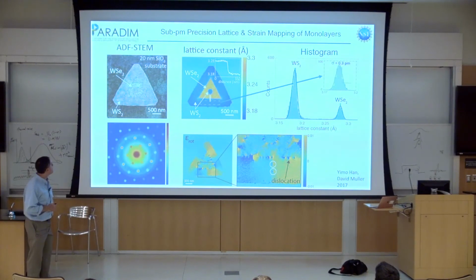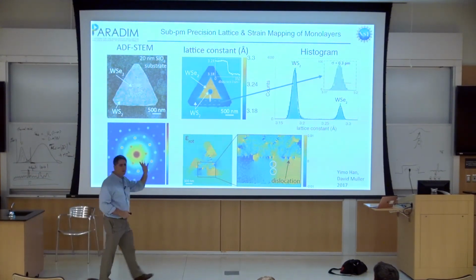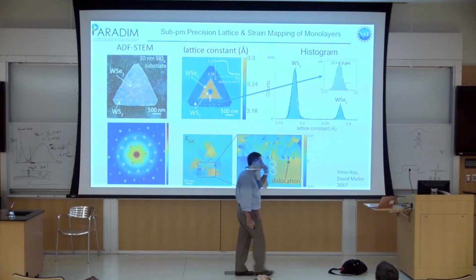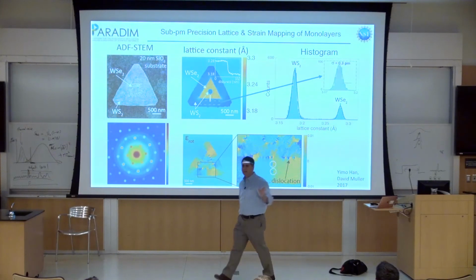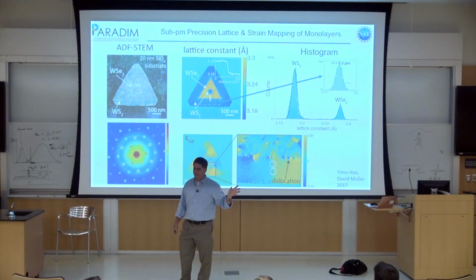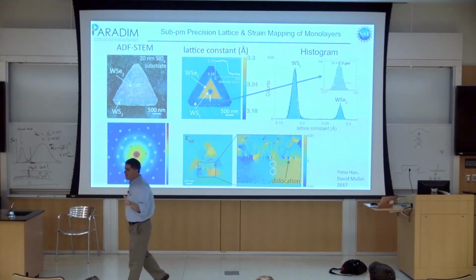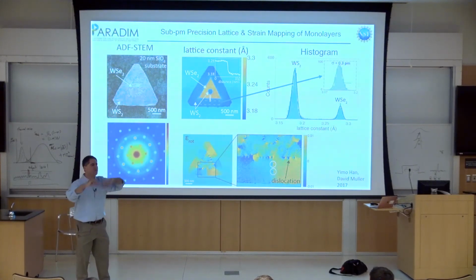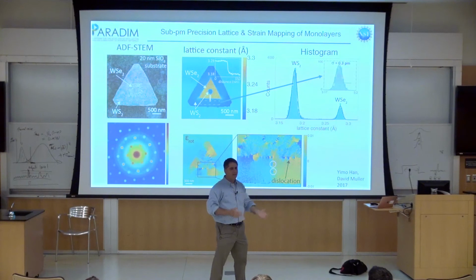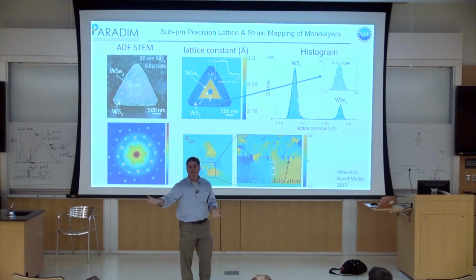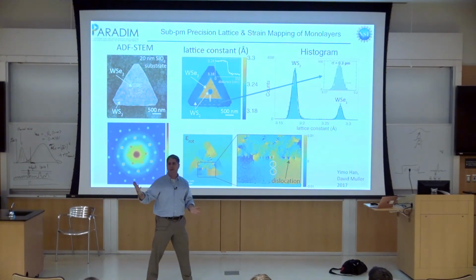I think in the interest of time, I should stop there. The two things I want you to remember. First is from the detectors. If I have n counts on the detector, what's the noise? Square root of n. Great. So if you've only got 4 counts in the channel, I've got 50% noise in my image. You're not going to be happy.